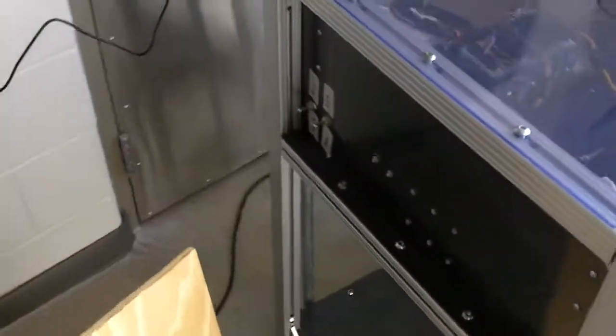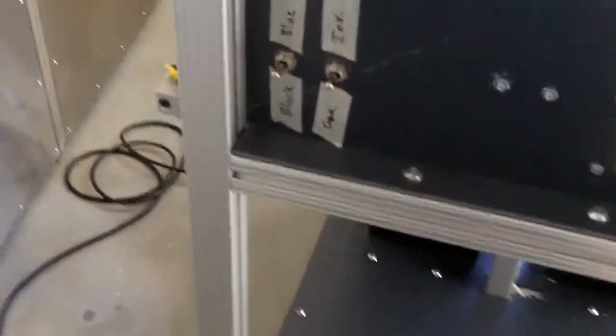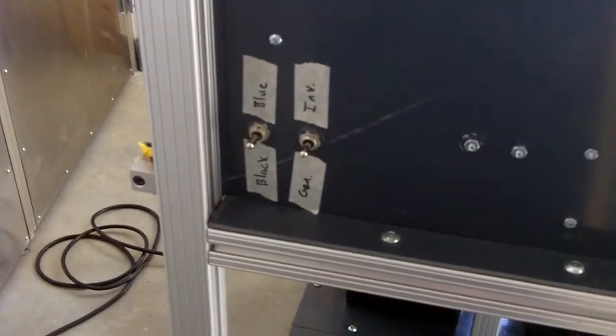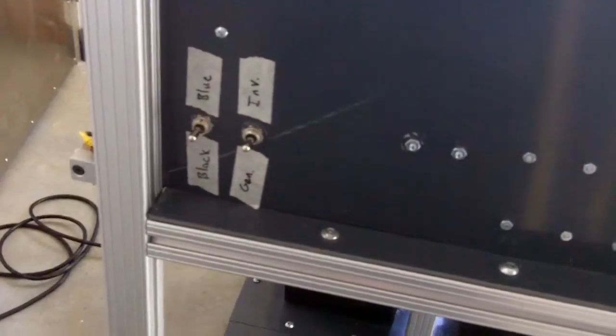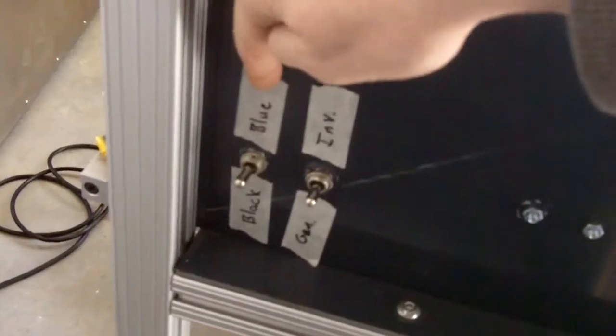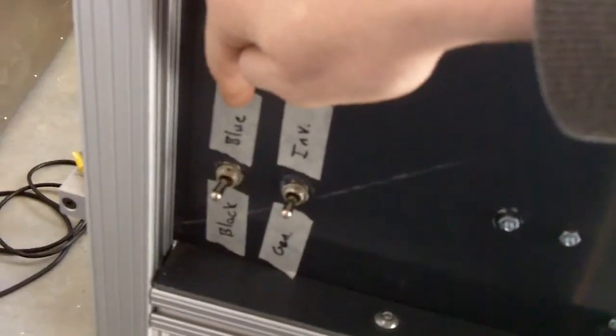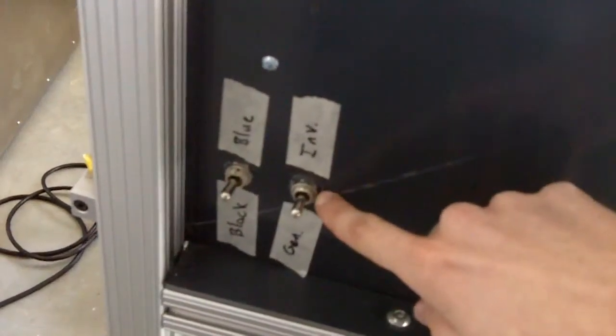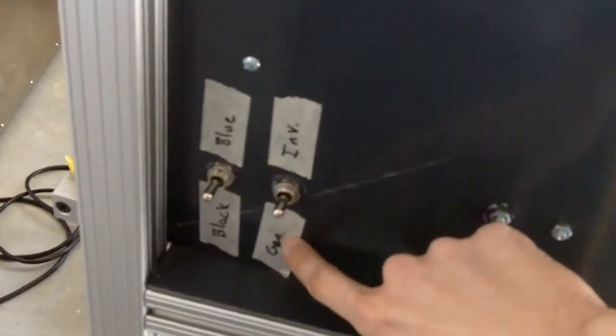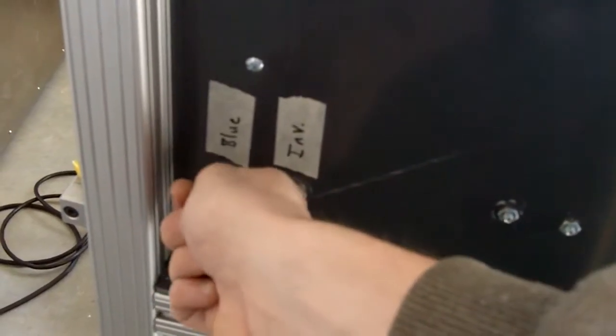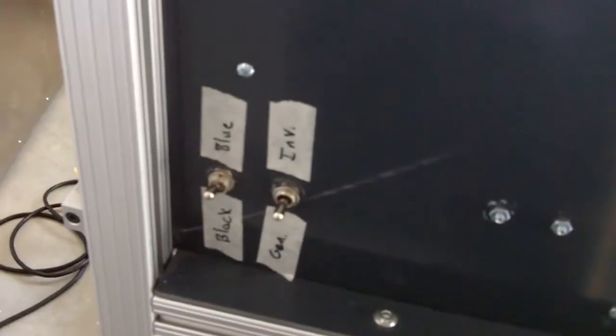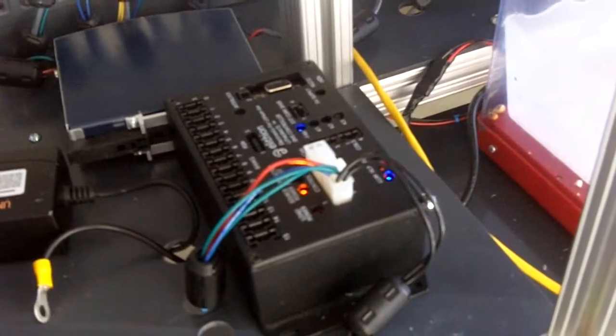The first new feature is that we have two main toggle switches as opposed to the original 14. The two toggle switches are used to turn on the Ames inverter and the CRIO and the AC supply for the relay module. The switch on the left, you can see the top is blue. If you switch that switch up then it turns on the Ames inverter with the blue lead acid battery. The bottom turns it on with the black lead acid battery. The switch on the right decides whether you are actually going to take the AC power from the inverter or from the generator. I am going to turn on the blue lead acid battery to the Ames inverter because this also powers up our battery management system. You can see we have our lights shining. Our battery management system is on. There are faults because the battery pack is not currently connected. Once the battery pack is connected then those faults clear.